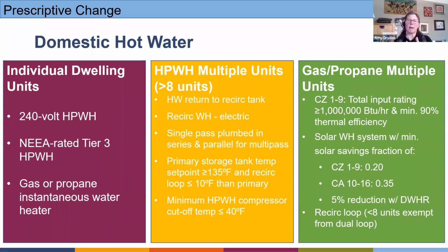And then on the right, you have gas and propane that are serving multiple units. So note that you don't have that kind of 8-unit limit here. There are some requirements in terms of our input rating, right? And 90% thermal efficiency is what we're looking for.